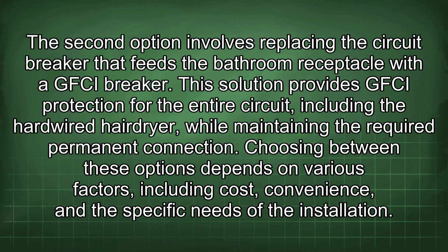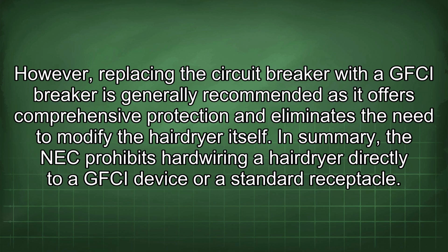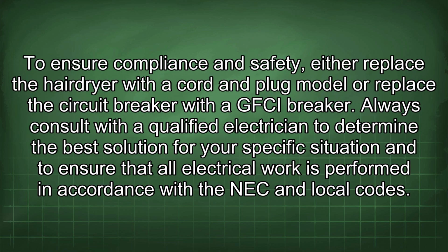Choosing between these options depends on various factors, including cost, convenience, and the specific needs of the installation. However, replacing the circuit breaker with a GFCI breaker is generally recommended as it offers comprehensive protection and eliminates the need to modify the hairdryer itself. In summary, the NEC prohibits hardwiring a hairdryer directly to a GFCI device or a standard receptacle. To ensure compliance and safety, either replace the hairdryer with a cord and plug model or replace the circuit breaker with a GFCI breaker. Always consult with a qualified electrician to determine the best solution for your specific situation and to ensure that all electrical work is performed in accordance with the NEC and local codes.